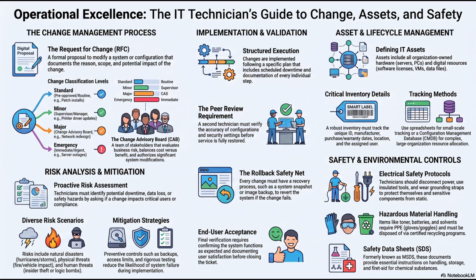But the complacency of experienced technicians is a massive risk factor, because they've done it a million times. But you are dealing with high-voltage power supplies capable of delivering lethal amperage. The manual dictates the mandatory use of electrically insulated tools and requires technicians to actively test voltage levels with a multimeter before touching any internal components. And work environments and hands must remain completely dry, because moisture and electricity are a deadly combination.